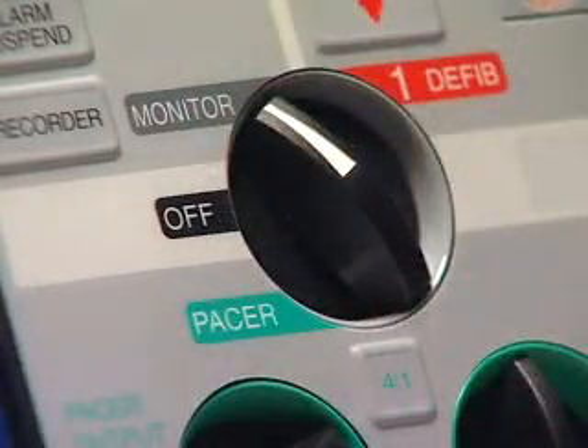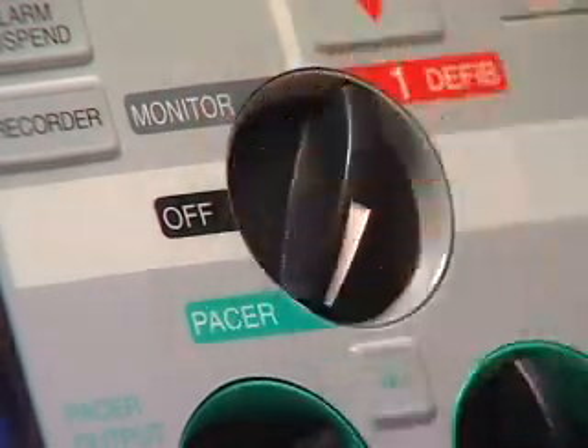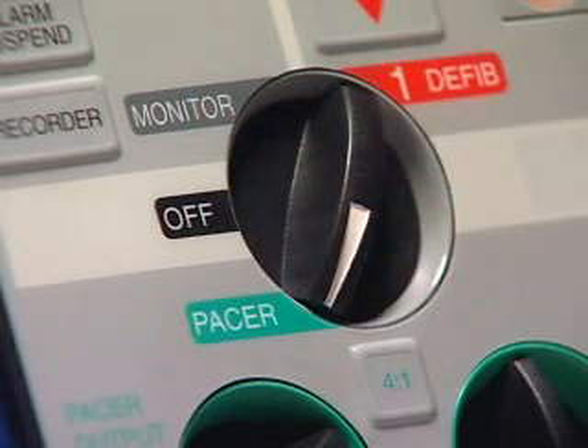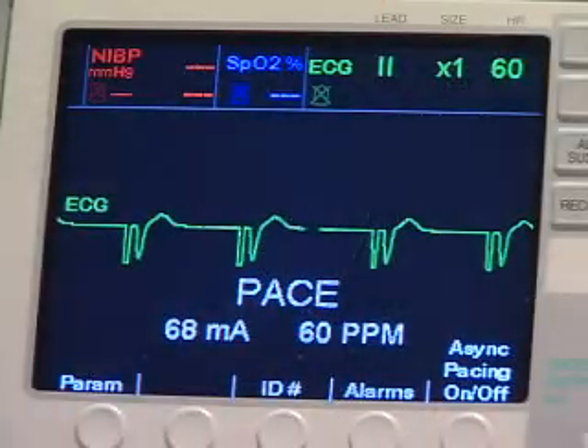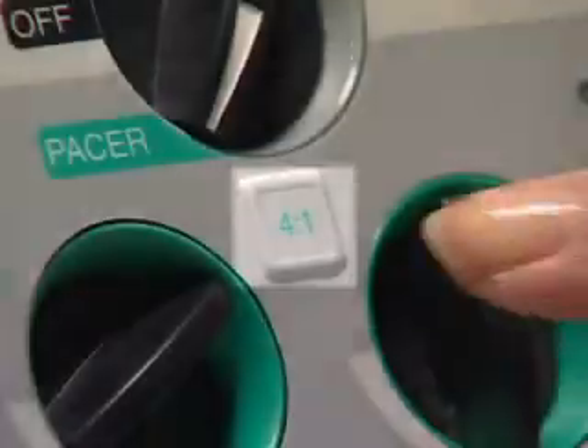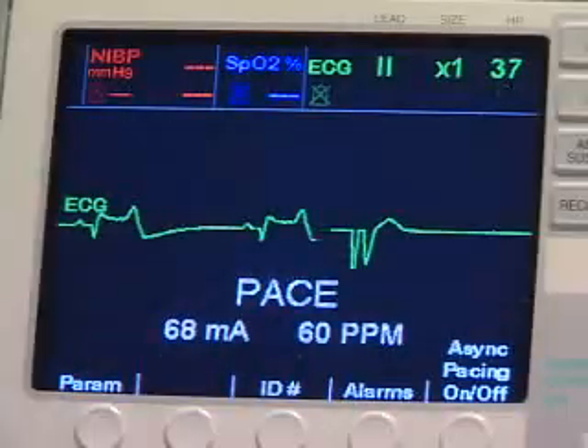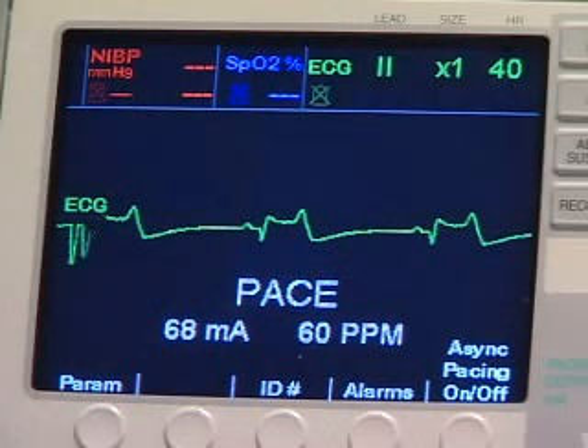When the E-Series is switched out of pacer mode into either defib or monitor mode for less than 10 minutes, and then switched back to pacer mode, the pacer settings will remain unchanged. You can check your patient's underlying rhythm by pressing and holding the 4-to-1 button. This button suppresses 3 out of 4 paced beats.